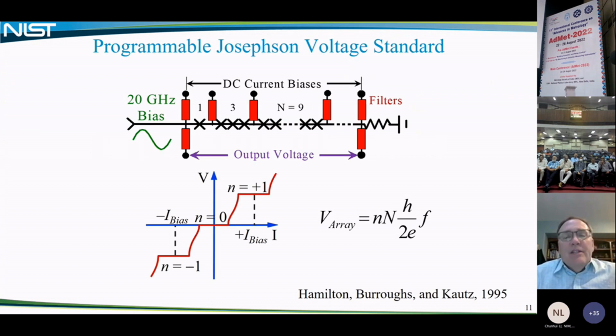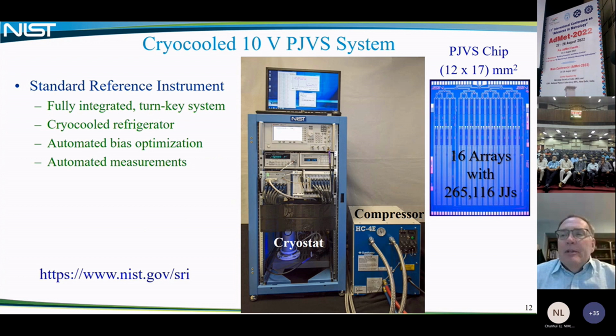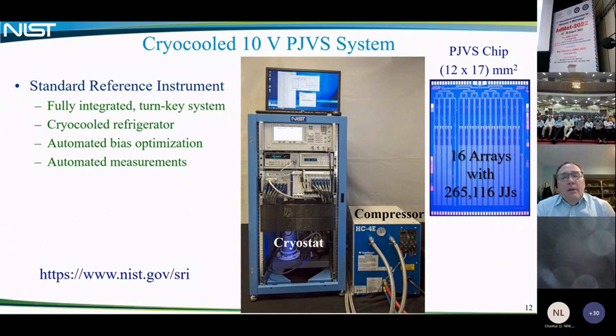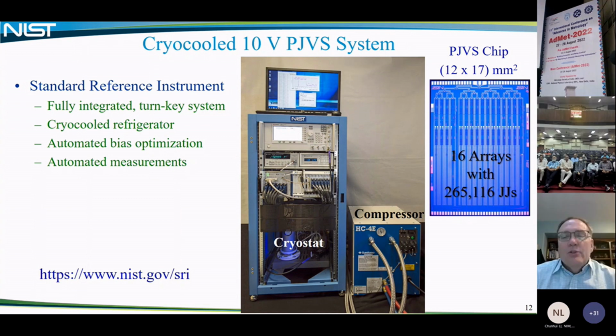It is based on a series array that is divided into subarrays of smaller numbers of junctions, and we change the bias on those smaller subarrays to either the -1, 0, or +1 step, and can program one of those three states. And then the output voltage can be programmed by changing the number of junctions that are biased on a particular voltage. Many years of advances to develop different types of junctions and microwave circuits, and also instrumentation and cryogenics, have resulted in the current version of our standard reference instrument, which is a cryo-cooled 10-volt PJVS system. And lots of software has also been developed to make this instrument useful.